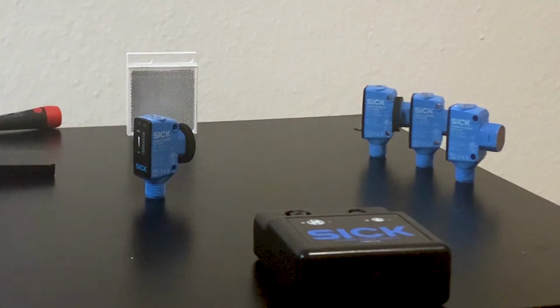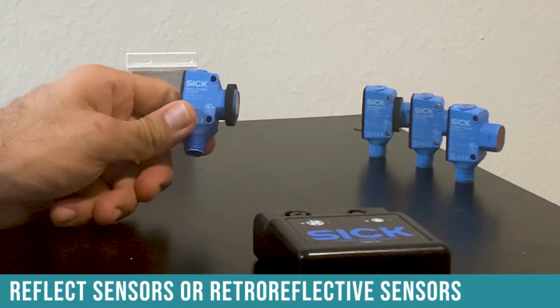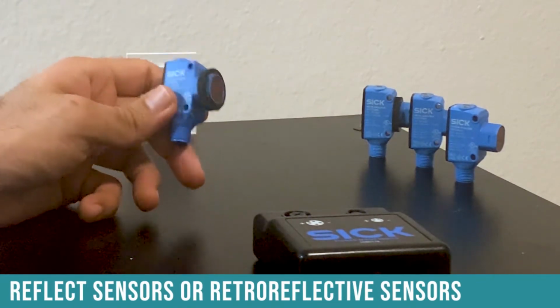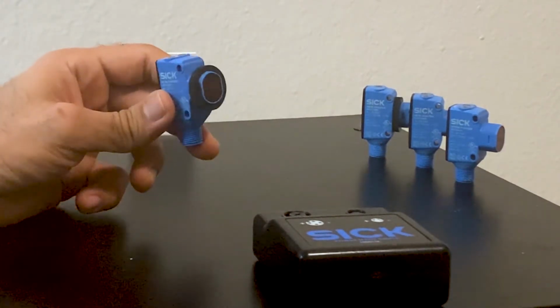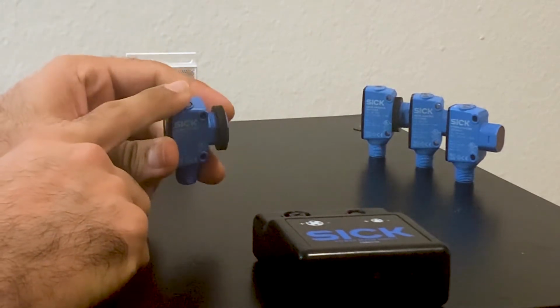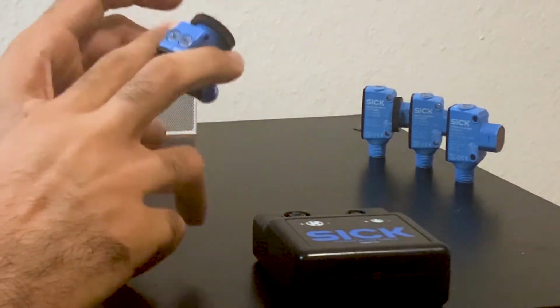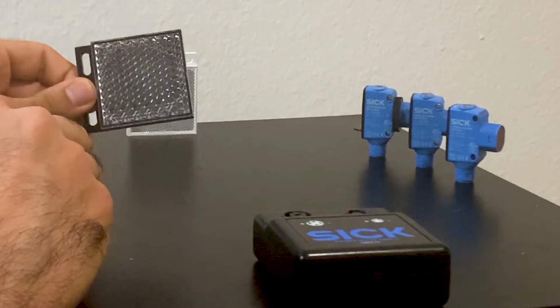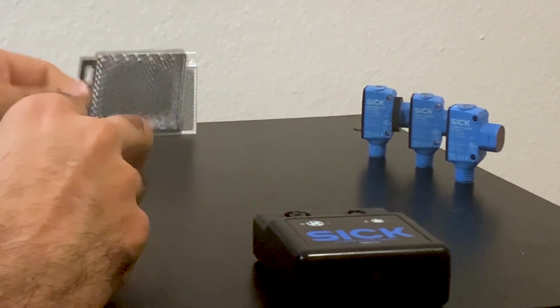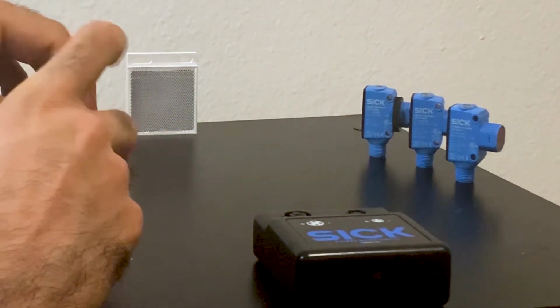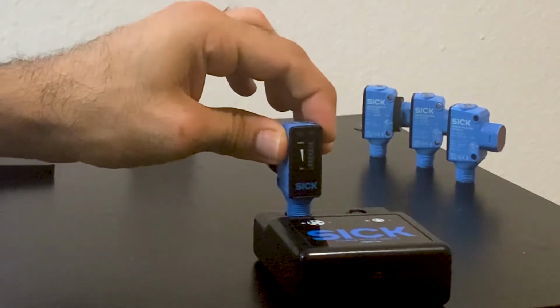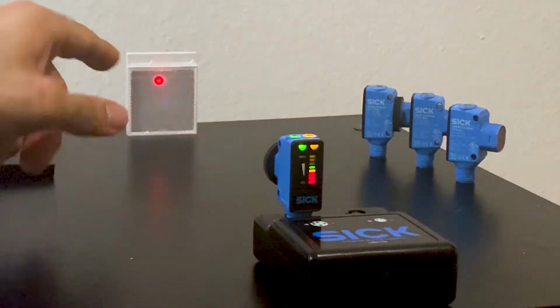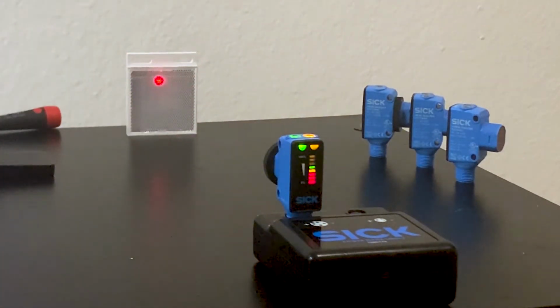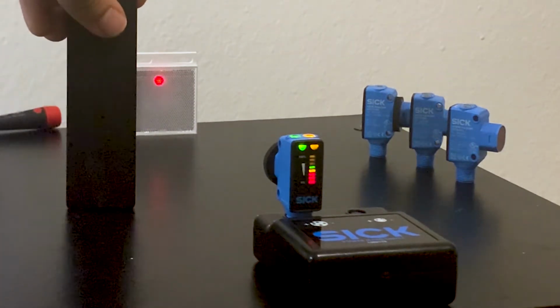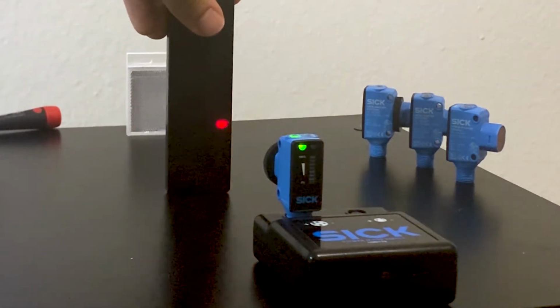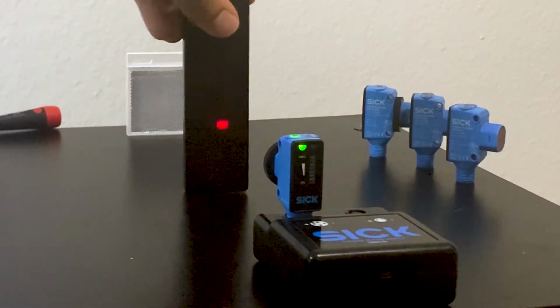The second technology is reflect sensors, also called retroreflective sensors. Unlike ThruBeam sensors, they have the sender and receiver in the same body, but you do need a reflector or reflective tape on the opposite side to complete the light path. Right now you can see the light path is completed by the reflector, and as soon as any object obstructs the path of light, the output is triggered.